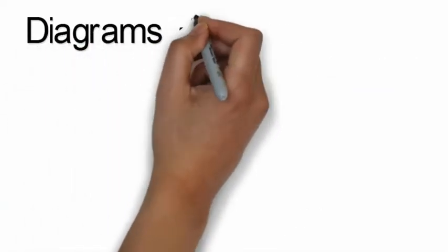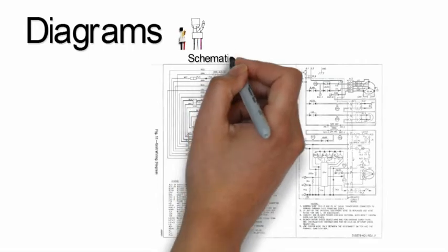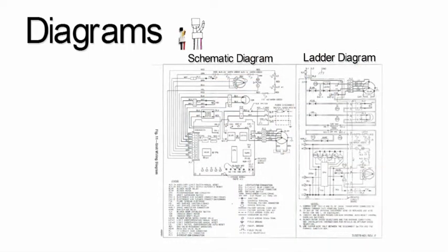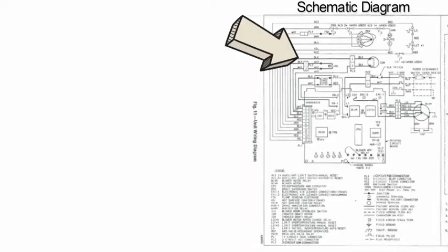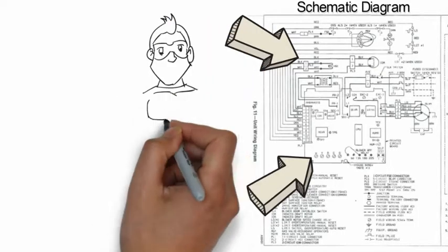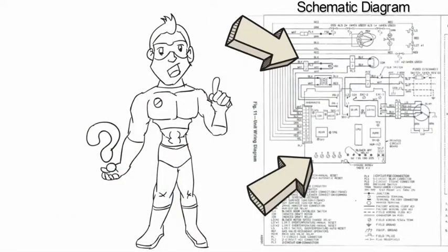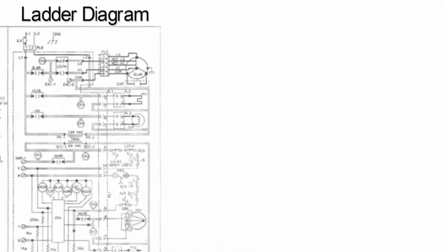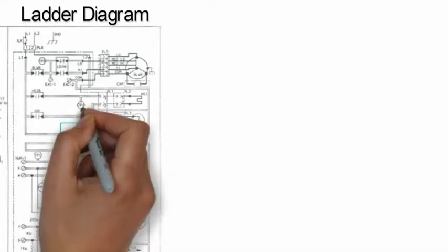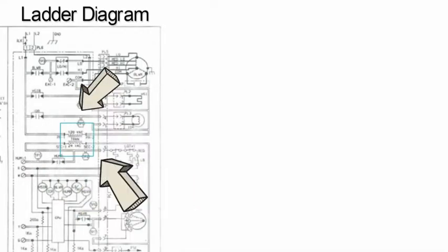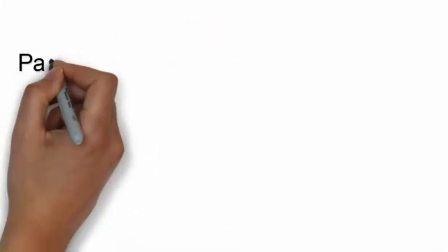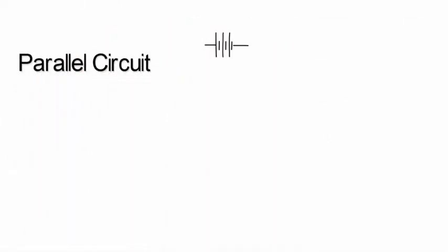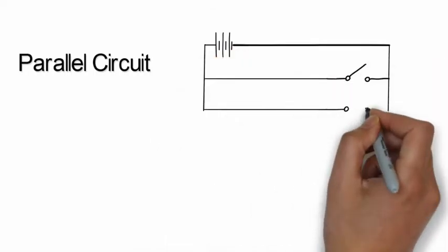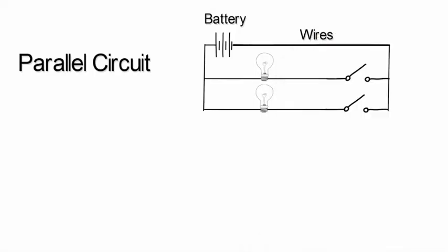Diagrams. Appliance wiring diagrams show the connection points of each wire used. These can be schematic or ladder diagrams. Schematic diagrams show how all working components are connected together, which includes the connected wiring. This can be helpful when troubleshooting problems. Ladder diagrams show the components and their location on the primary or secondary side of the transformer. Most loads are wired in parallel across their voltage source because a load in parallel is unaffected by other loads unless those loads short out.